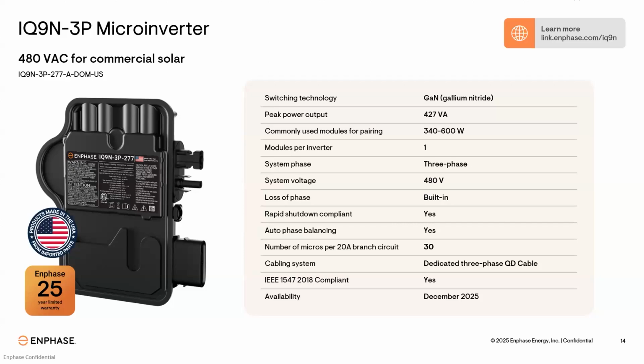The technology inside this microinverter is gallium nitride, which allows the switching inside of it to be more efficient and allows the microinverter to operate cooler and be in a smaller form factor. So it weighs less and it's very similar in size to what our residential microinverters are. And again, this is the IQ9N 3P 277 480 volt microinverter that is available for pre-orders today. And we will be fulfilling those pre-orders near the end of this month, probably the next couple of weeks.